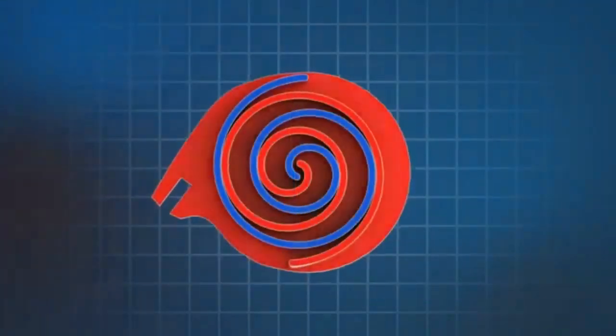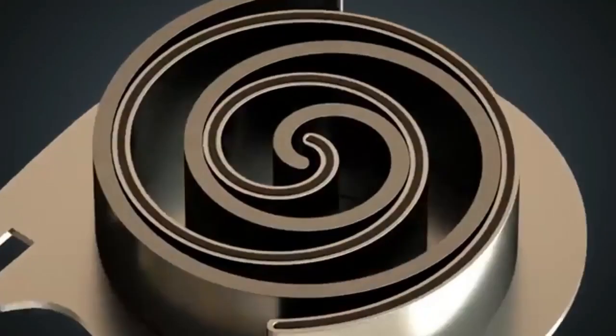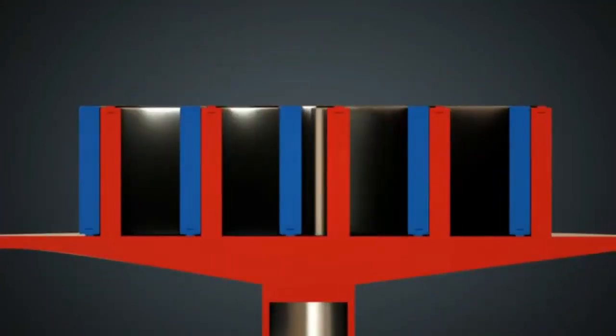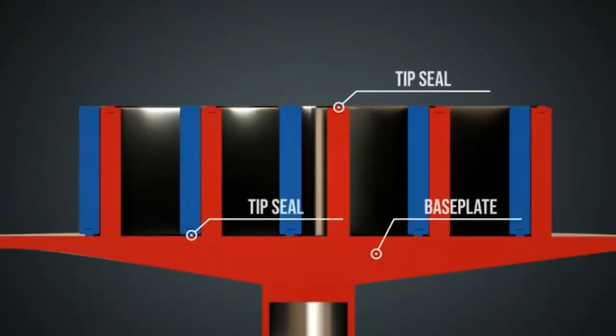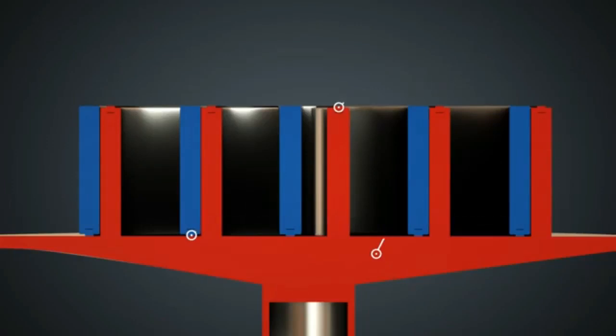Axial sealing can also be designed in various ways. One possibility is the use of a floating tip seal. These are present on both scrolls and are pressed against the base plates by gas pressure. In this animation, the upper base plate is not shown.